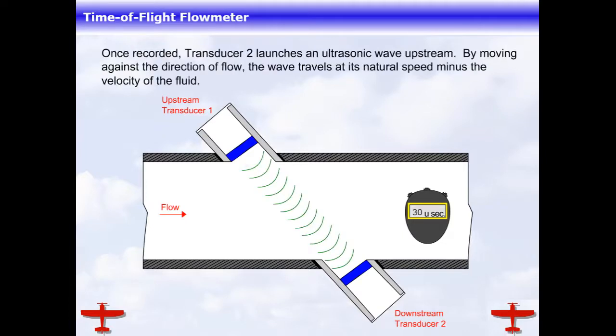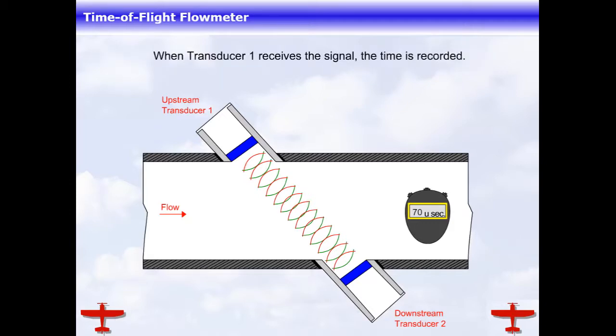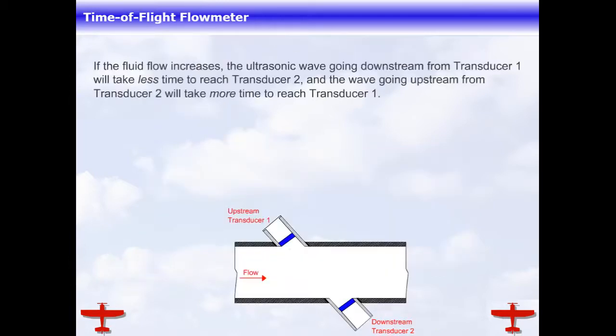Once recorded, transducer 2 launches an ultrasonic wave upstream. By moving against the direction of flow, the wave travels at its natural speed minus the velocity of the fluid. When transducer 1 receives the signal, the time is recorded. If the fluid flow increases, the ultrasonic wave going downstream from transducer 1 will take less time to reach transducer 2, and the wave going upstream from transducer 2 will take more time to reach transducer 1.